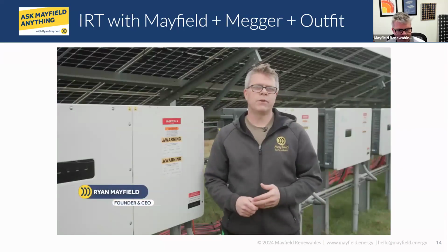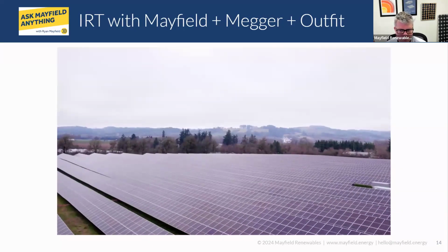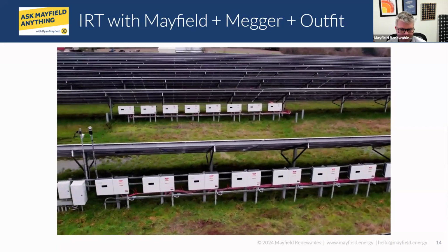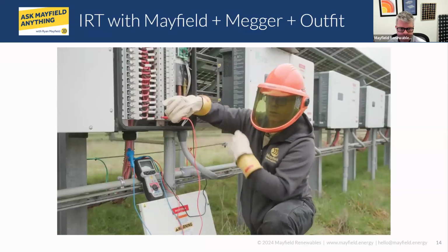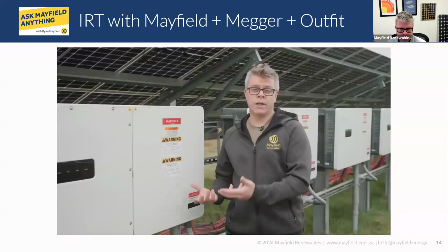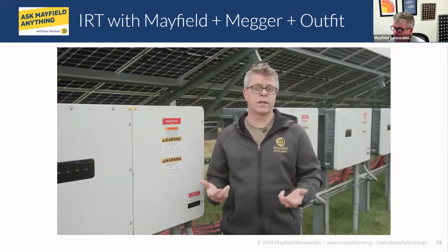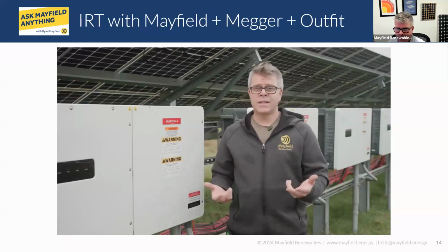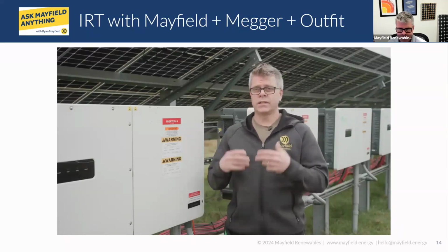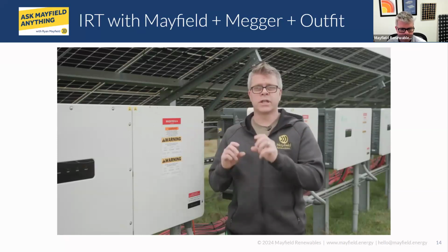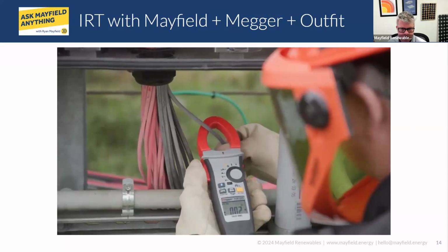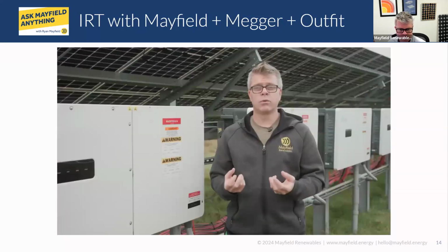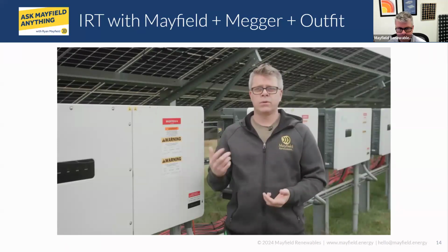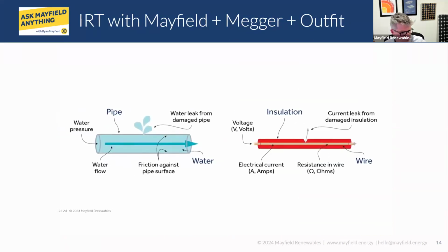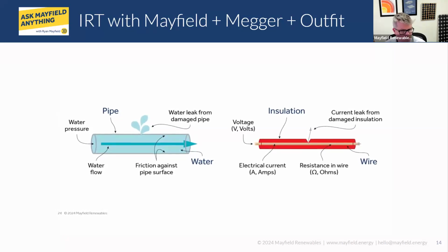Hi, my name is Ryan Mayfield of Mayfield Renewables, and today we're out here at this 2 megawatt ground mount PV array to talk to you about insulation resistance testing and how to perform those tests and interpret those results in the field, so that you can understand if there's anything you need to do in real time to maintain or fix any conductors. As the name implies, an insulation resistance test looks at the different circuits and the conductors to make sure that the insulation around the wires themselves is in good working order. We very often use water as an analogy in our electrical systems, and this is a lot like pressurizing a water pipe and looking for a leak.